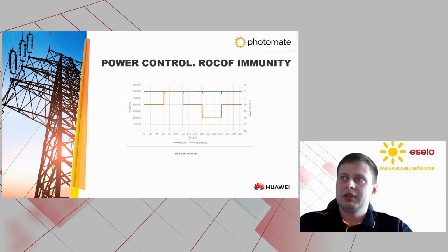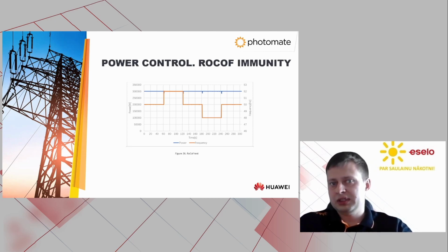Very common also request about ROCOF. ROCOF is rate of change of frequency. So the inverter must stay connected to the grid even if the rate of change of frequency is very high. If the inverter disconnects, the grid will lose a lot of active power, and the problem of decreasing frequency will become bigger.